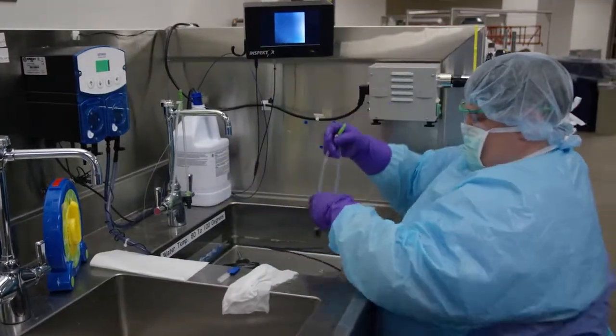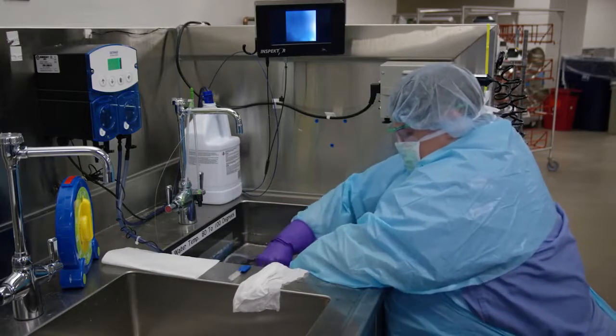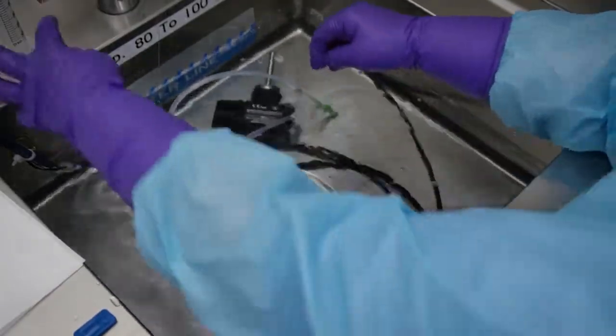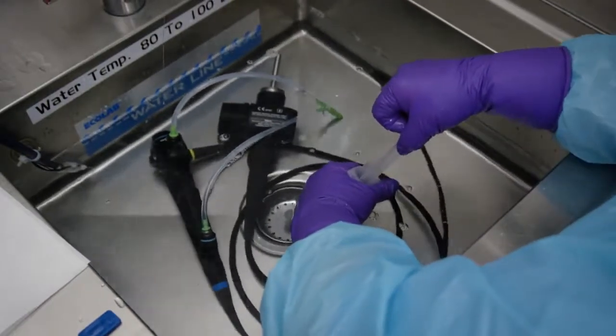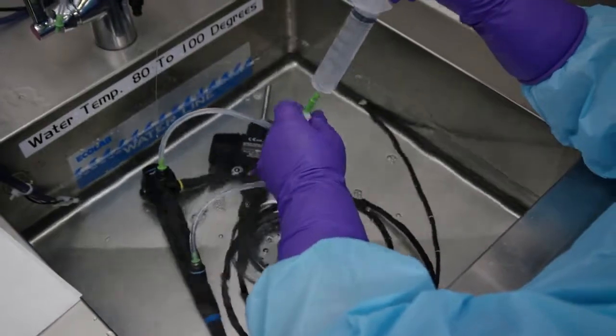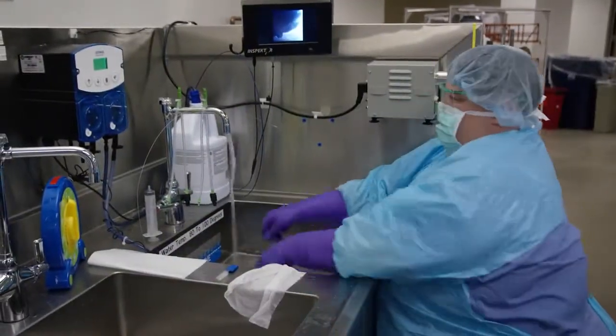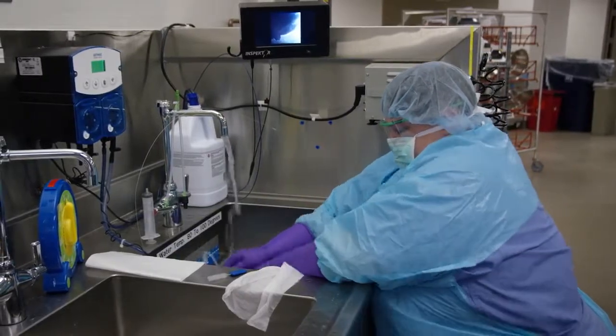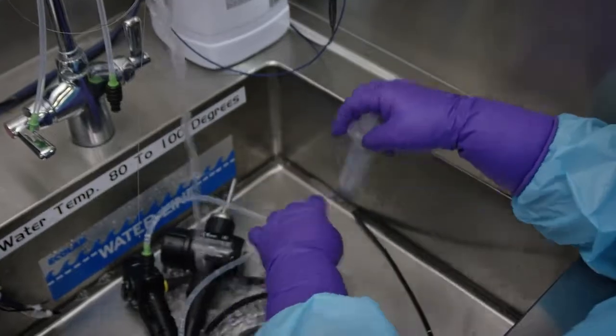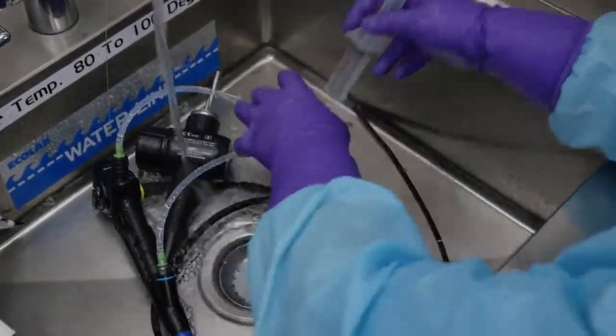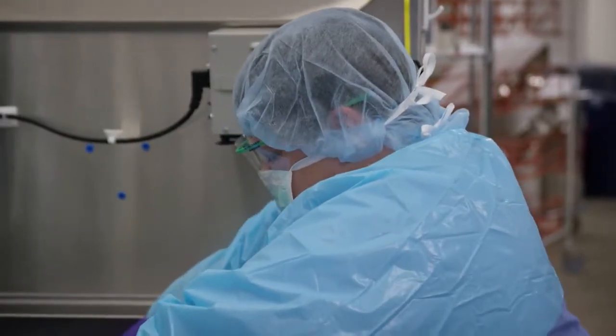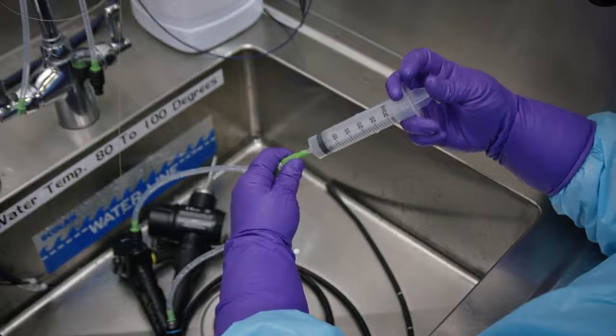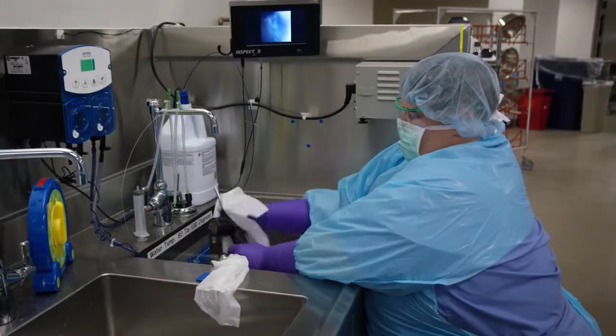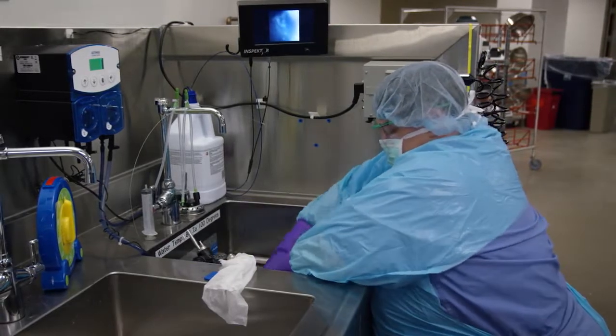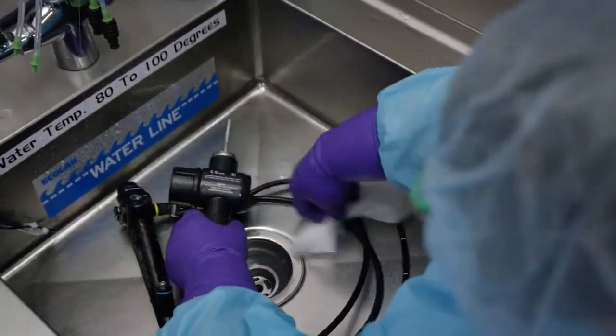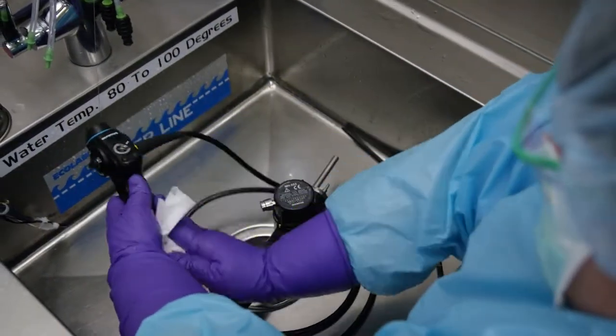Next, facilitate flushing by attaching the channel adapter to the ports. If indicated by the manufacturer, attach tubes required for irrigation to suction, biopsy, air and water channels, elevator, and auxiliary channels. Thoroughly rinse and flush channels with water until all cleaning solution is visibly removed. Repeat the cleaning, brushing, and rinsing steps until all visible debris is eliminated. Purge channels with air using a syringe or instrument air per IFUs to evacuate residual rinse water. Dry the exterior with a lint-free cloth to remove any residual detergents or water droplets, which can dilute sterilants or high-level disinfection chemicals. Throw away disposable brushes.